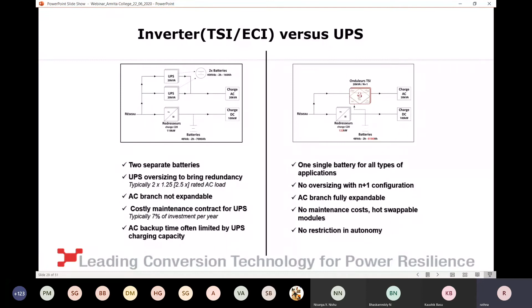Telecom operators need more availability, no single point of failure, and good noise rejection, with no transfer time when AC is not present. They need a highly reliable product with high mean time between failure. For maintainability, it should be modular, hot swappable, and lightweight enough that even a normal person can handle it. For operationality, it should support expandability and handle load variations or inrush currents.